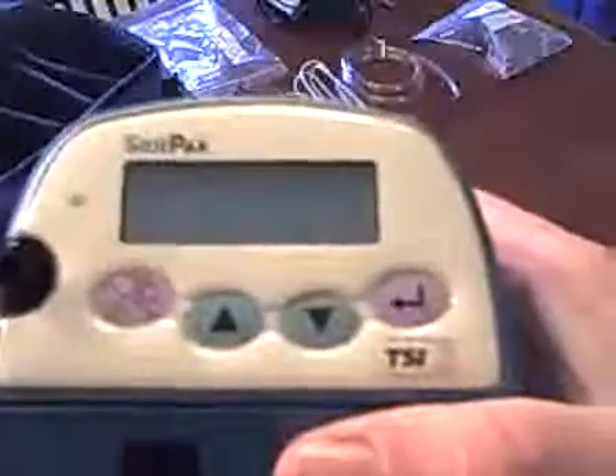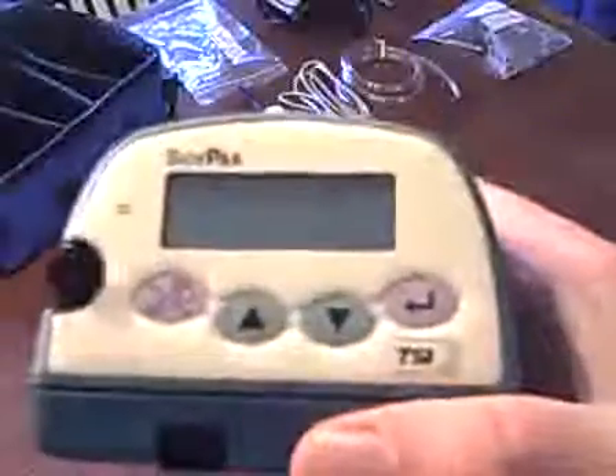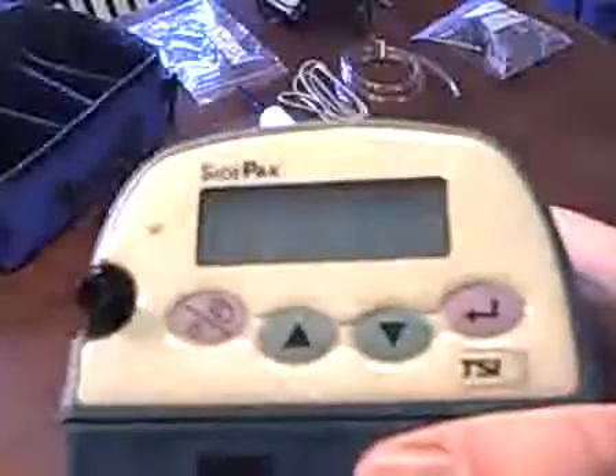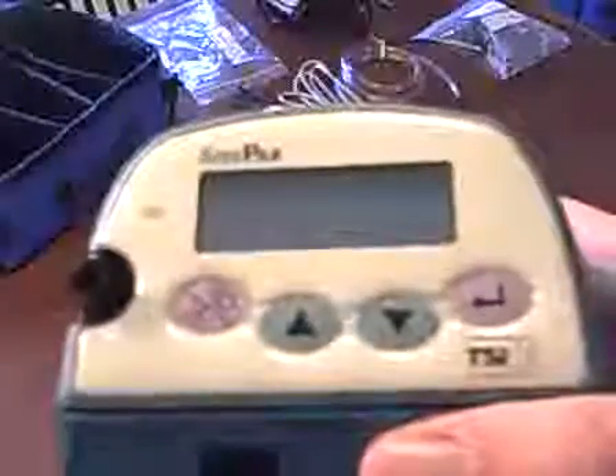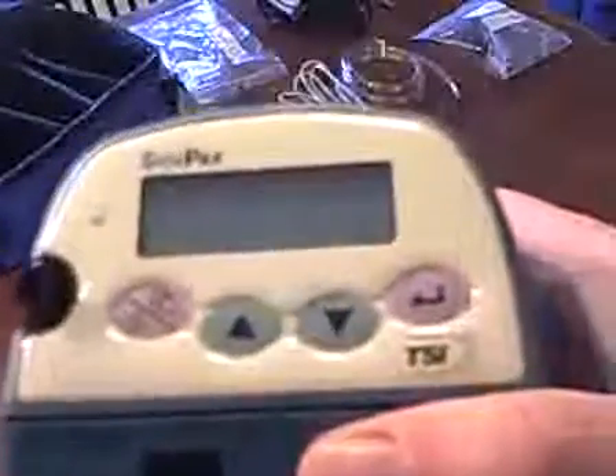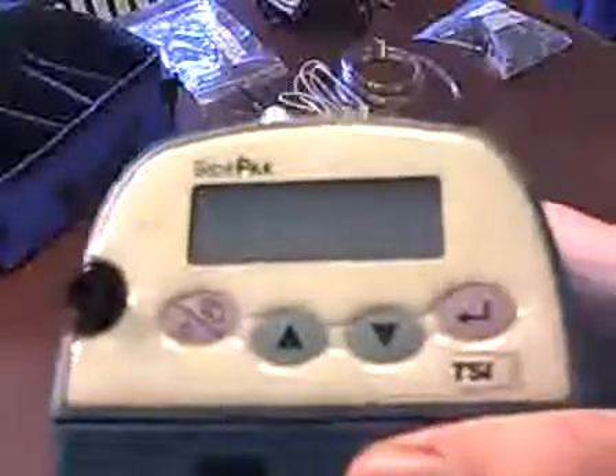So 0.001 milligrams per meter cubed would be equal to 1 microgram per meter cubed. Now I think you can hear the pump. It's getting pretty loud. It's fairly warmed up, and the display now says survey mode. So once we're in survey mode, that means we're taking data. We can start to log data if we want to, or we can just observe what's on the LCD display and write those numbers down.